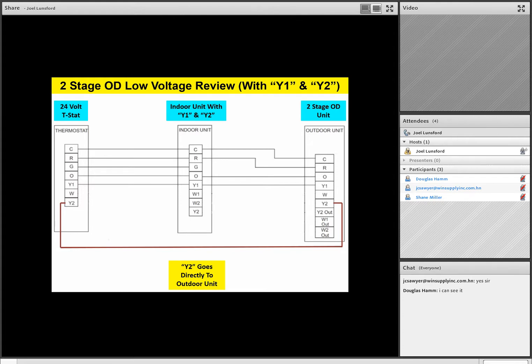It could be the result of staging. It could be the result of intelligence on the outdoor unit, like on the TH16, for instance. The outdoor unit is going to determine when you're going to have second stage airflow. So Y2 from the thermostat directly to the outdoor unit is also a normal scheme if you've got the outdoor unit staging second stage airflow. Then from the outdoor unit, we're going to have W1 out, and that'll come into the indoor unit, and that'll be first stage auxiliary heat.